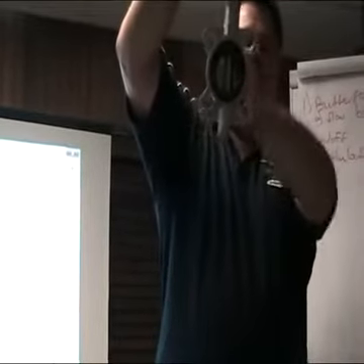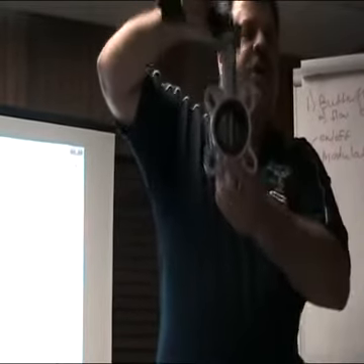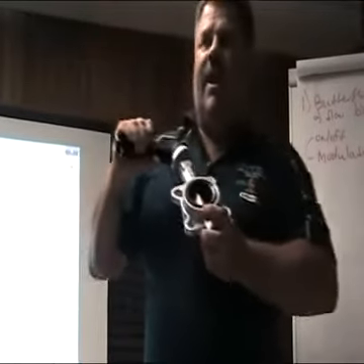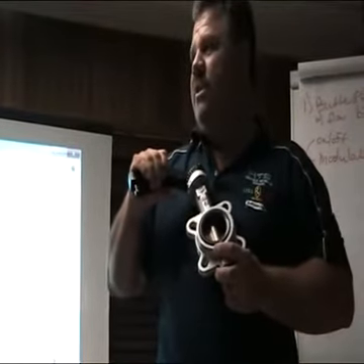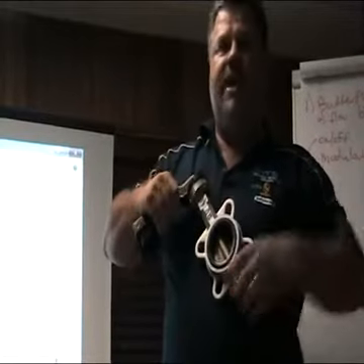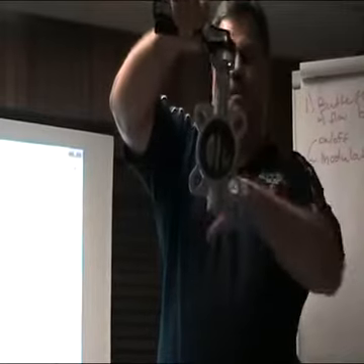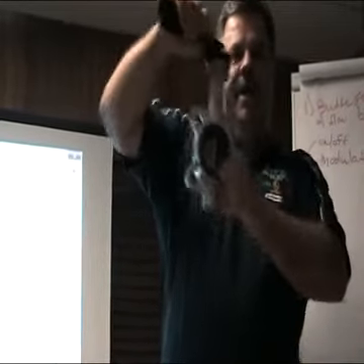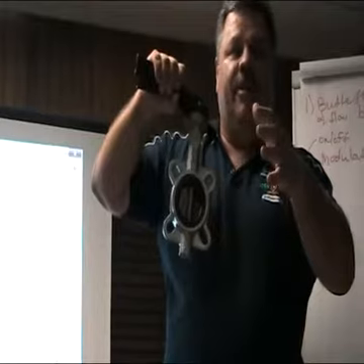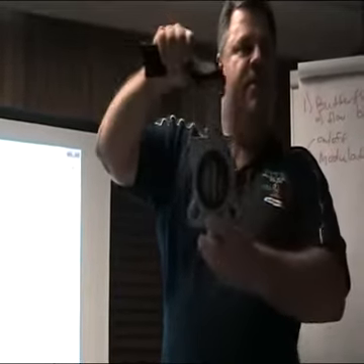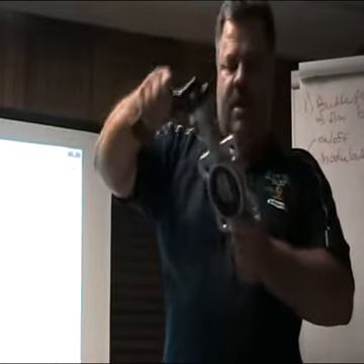Yeah. Just getting further to this, you also get lug type. Lug type means there's more of these holes around this body. Alright? Usually you will use lug type butterflies, in my 20 years experience, maybe 4 or 5 valves, usually at the end of a pipe, where you need good support. I mean, you're supporting it with 4 bolts in the line. At the end of the pipe, if there's high volumes coming through, you need more support, you would use a lug type butterfly. Alright? Okay, any questions on low pressure butterfly valves?